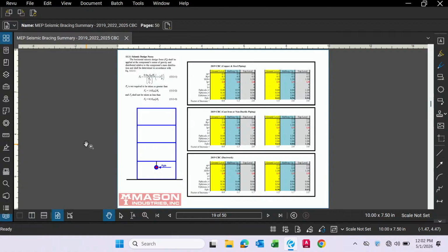According to that formula, it takes into account the location of the facility, how far it is from a known seismic fault, and how high up the structure the component is anchored, because as you go higher in the building, the seismic force increases due to more swaying on top. It also accounts for material types, flexibility, and how well the component responds in a seismic event. For example, ductile piping like steel or copper pipe is more flexible compared to cast iron piping, so when designing for cast iron, you have to adjust the seismic force factor to increase the seismic demand.